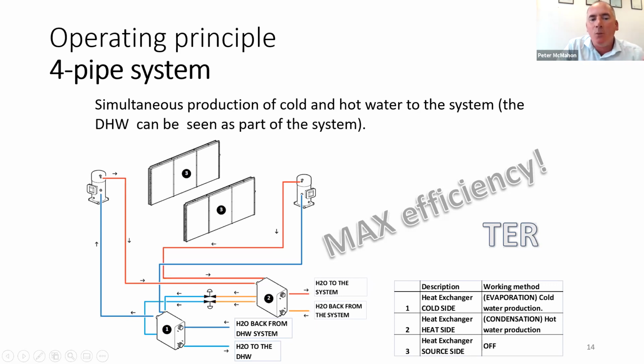So let's again say we have our 300 kilowatts cooling capacity, we have our 400 kilowatts heating capacity, that's a combined workload of 700 kilowatts. We haven't added any compressors. We're going to say our input power is the same of 100 kilowatts. So now our TER, what we get out versus what we put in, is 7. Okay, so I'm hoping this is what should be getting your attention now. And this is really what it's all about. So we have more than doubled our energy efficiency ratio by recovering that energy.